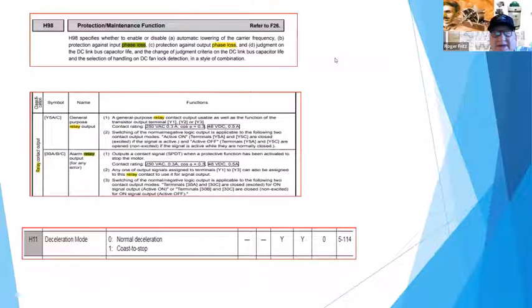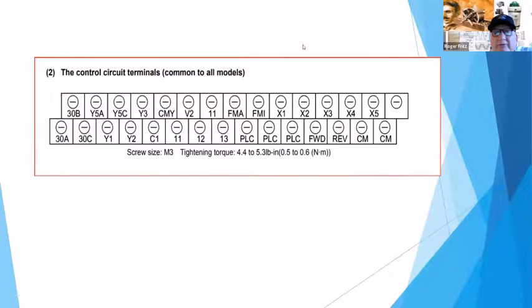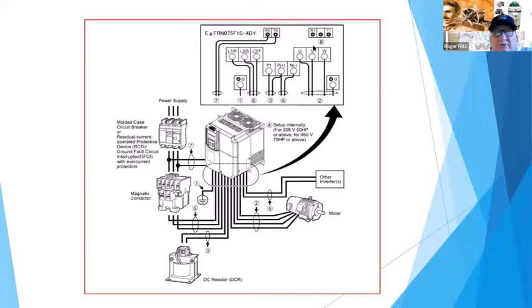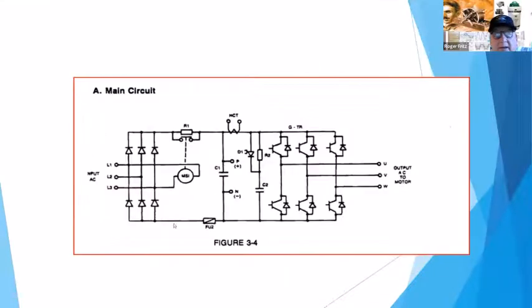I'll tell you about that, because sometimes you want to use the VFD to take single phase input power and actually run a true 3-phase motor successfully. And so you're able to take the power source here, and instead of using all 3 phases input, you're able to use 2 phases, normally line 1, line 3 only. You don't even hook up this one. We can still build DC here. The key factor is that these diodes will be carrying more current. So let's say a motor's 100 amps here on single phase, it's going to draw it through just 2 legs, not all 3 phases. So it's going to be 1.73 times that 100 amps. So it'd be 173 amps going through.